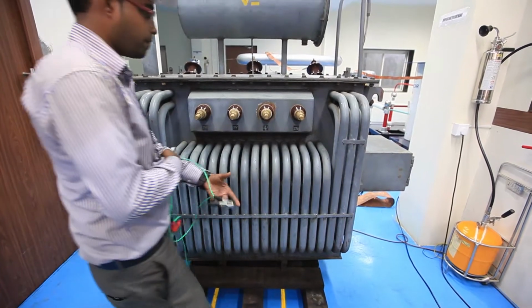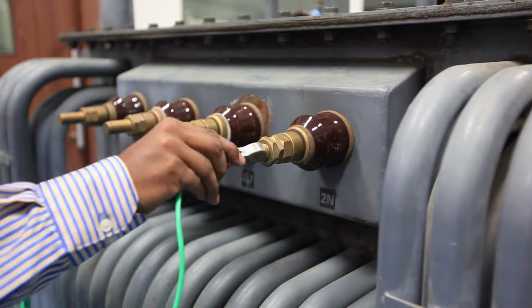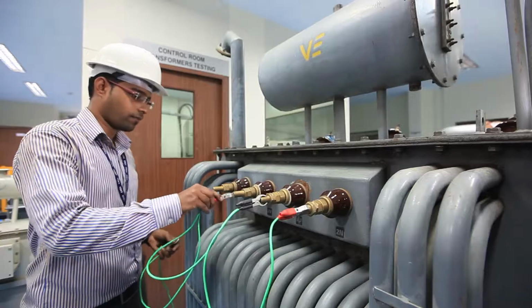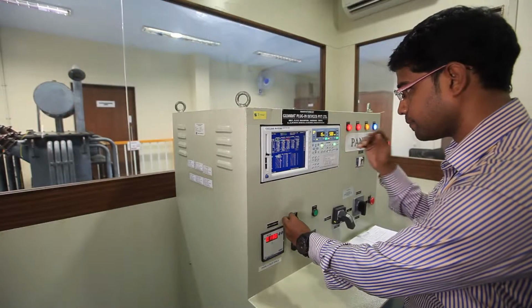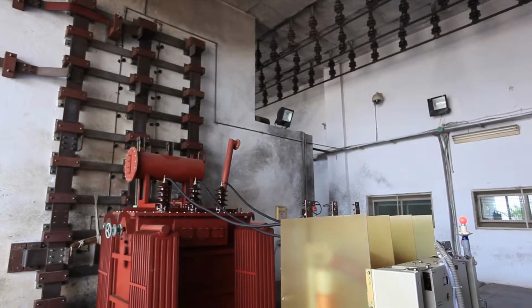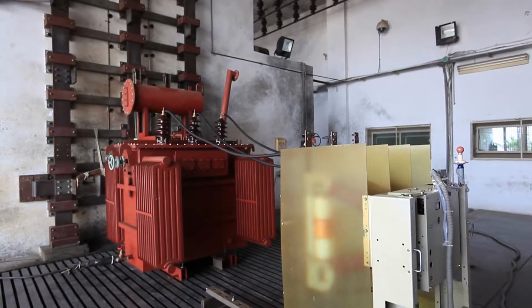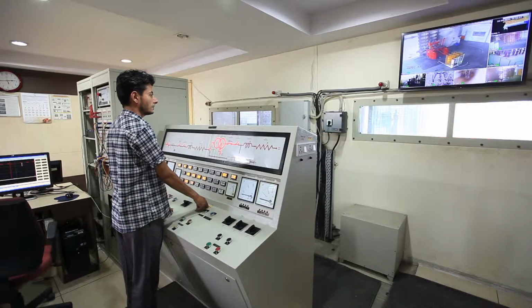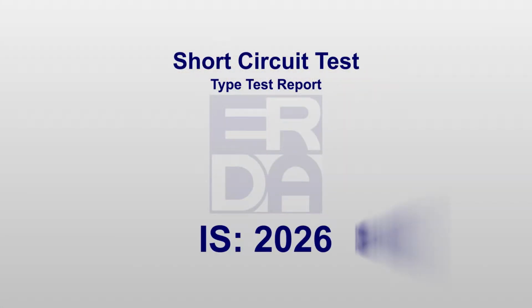The quality of 33 kV class distribution transformers, 200 kVA, can be ascertained through type tests. We arrange for short circuit test at our main laboratory complex at Vadodara and issue complete type test report according to IS 2026, IS 1180 and IEC 60076.